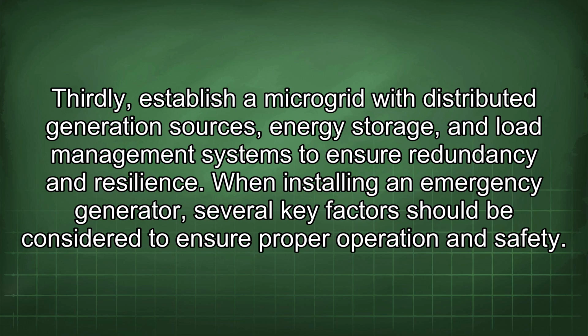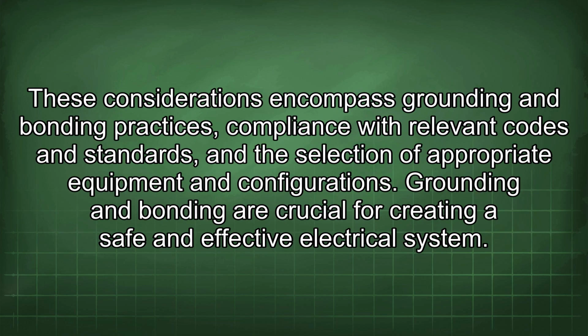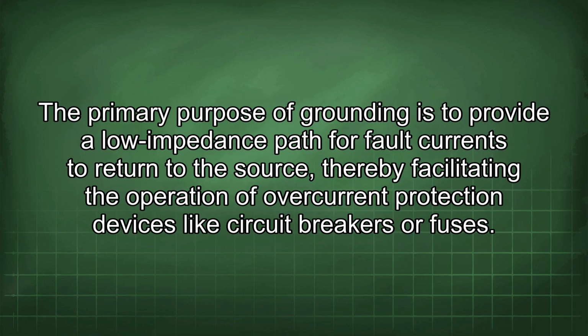When installing an emergency generator, several key factors should be considered to ensure proper operation and safety. These considerations encompass grounding and bonding practices, compliance with relevant codes and standards, and the selection of appropriate equipment and configurations. Grounding and bonding are crucial for creating a safe and effective electrical system. The primary purpose of grounding is to provide a low impedance path for fault currents to return to the source, thereby facilitating the operation of overcurrent protection devices like circuit breakers or fuses.